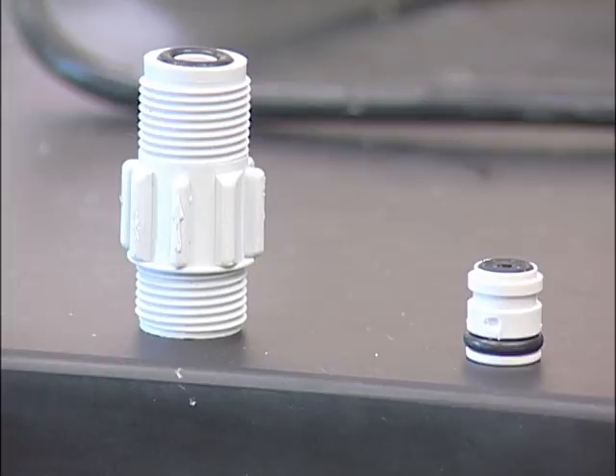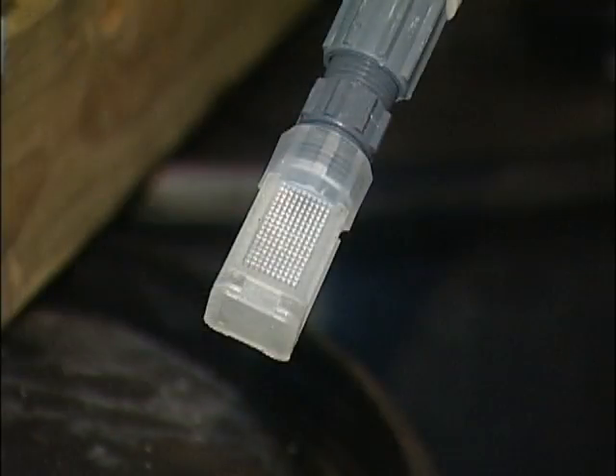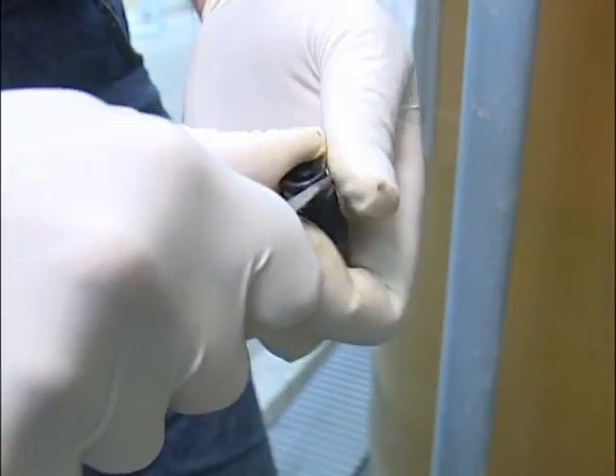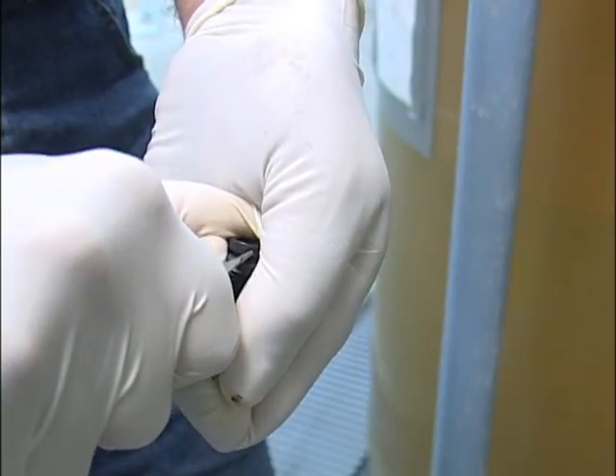Check valves are frequently accompanied by a foot valve, similar to the type shown here. The screen is used to protect the seat and ball so that material does not become lodged on the device, preventing the seal. The screens should be checked and cleaned periodically. There are also check valves on the diaphragm of the pump.